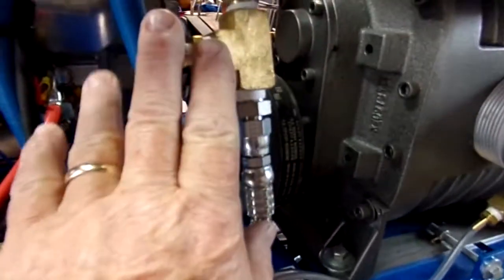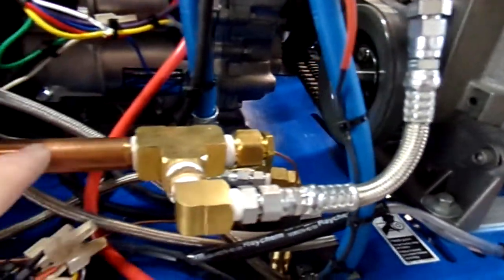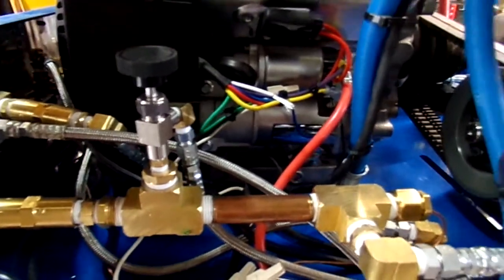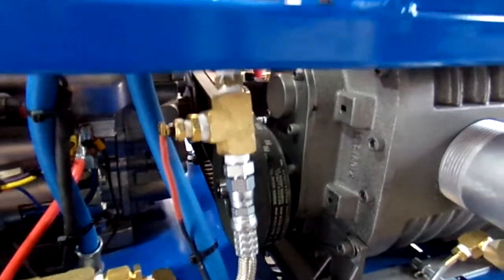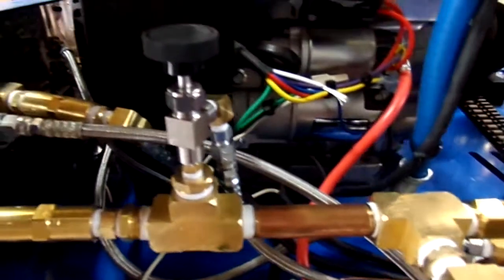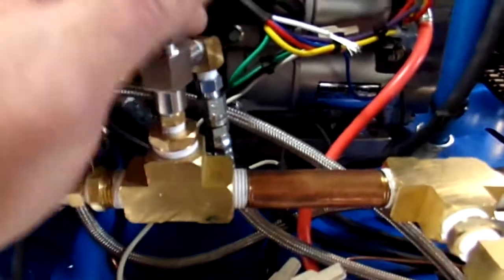So all of this is pretty straight up. The sender is downstream. This is basically, I would say, upstream, and this is downstream. So what happens is when the water flows across this, because you should always have water circulating in your heat exchanger. That way you don't have stagnation of temperatures and high-pressured hot water that could create a problem on your job, especially liability-wise, damage to your equipment, and possible personal injury to you and your customer. So the key is to always have circulation. And in doing so, this is downstream.